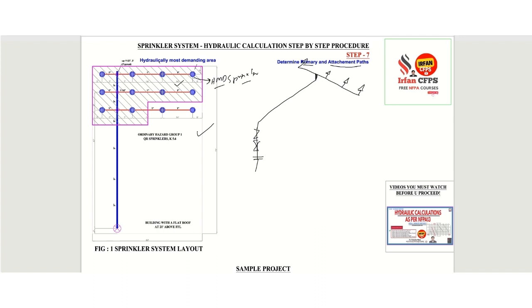Here also we'll draw this sprinkler. Again, here the pipe is raising after nine feet. These sprinklers are upright sprinklers. Since this is typical, I'm drawing the same thing. This is one more sprinkler. Here we have one more sprinkler. Also, we have two sprinklers at this particular location, so we are going to draw that sprinkler as well, and one more sprinkler here. So now we have drawn the isometric. This is the riser gate valve, and this is the check valve. This is the cross main, and these are the branch lines, and these are the upright sprinklers.